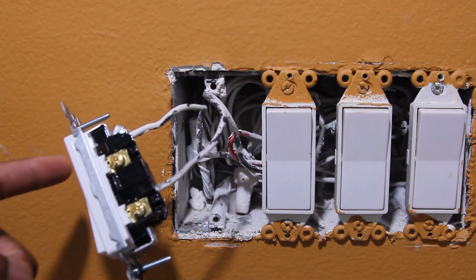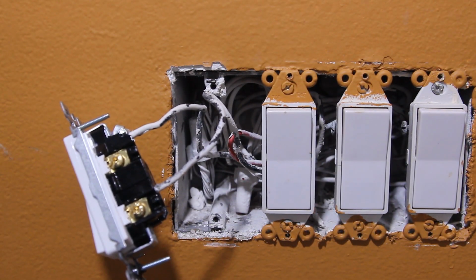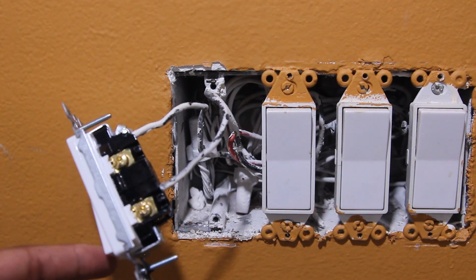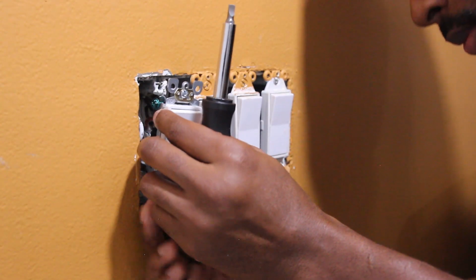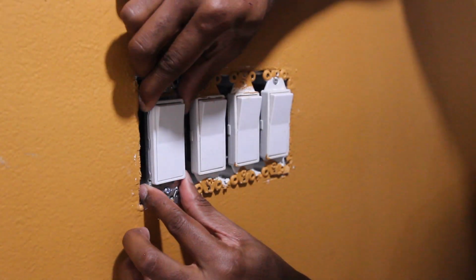At this point, you're able to flick the circuit breaker back on and test the switch to make sure it works. Once you confirm everything's working, turn the power back off from the circuit breaker just to be safe. Now you can install the switch back into the switch box and adjust it so it fits under the switch plate.